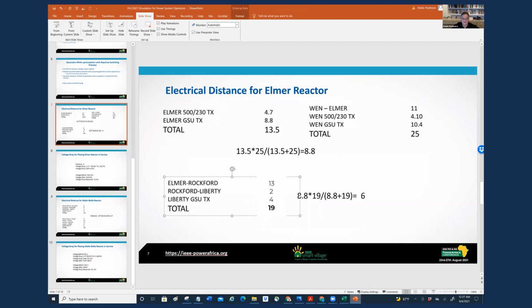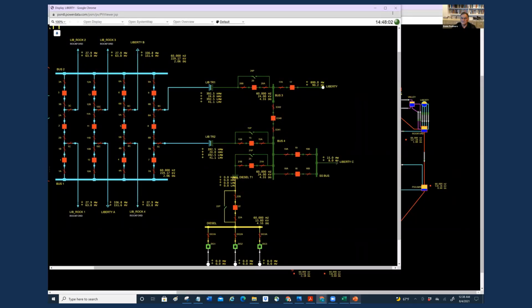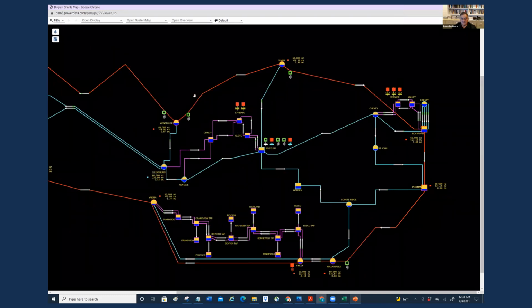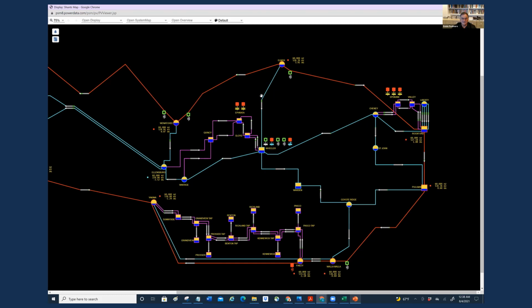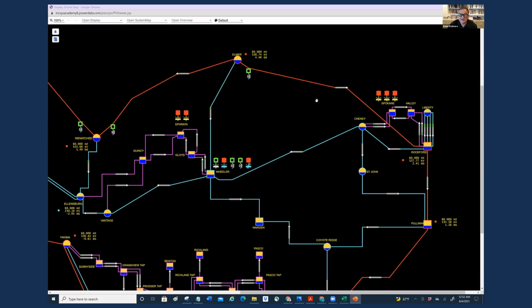And then this is the length of the 4 parallel lines at 230 into Rockford, and that gives us a 19. So what we simply do is we take these 2 lines, equivalent lines in parallel, go through the parallel reduction, and we get almost 9 miles. And then we take this one and do the parallel reduction again, or combination with the 19, and we get down to 6. So we're saying the equivalent distance from the 500 kV bus at Elmer, in terms of the parallel support that it's getting from all the generators here, and the generators here, is 6 miles.